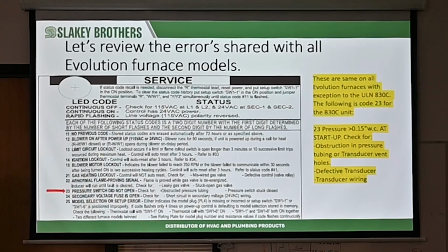There's 8 switches, and the very first one, you flip it on, and all you're doing is telling that circuit board, hey, can you tell me what faults you've had? Again, this is without using the comms, because you're just at the furnace, you're up in the attic, and I know what it's like to go up and down a ladder going in and out of an attic. So I'm not going to go up. I'm not going to go down. I'm just going to flip that switch and see what the past error codes are, because the complaint was no heat, right? Number 11, no previous fault code, just means there's no previous fault code in there.